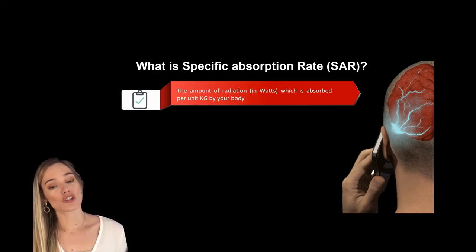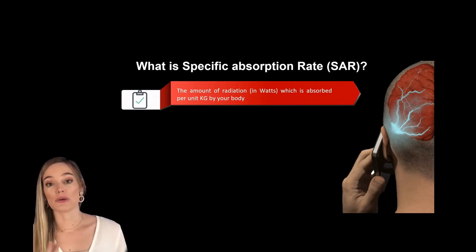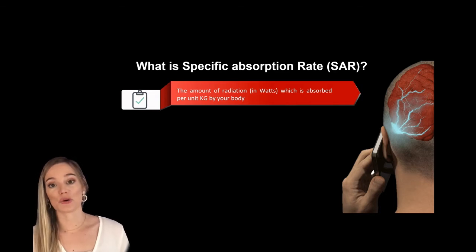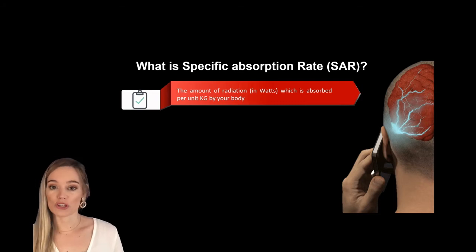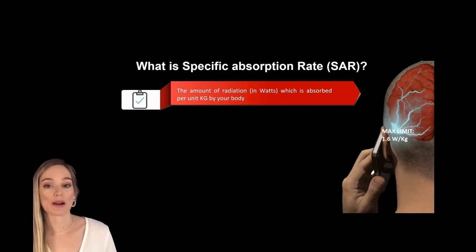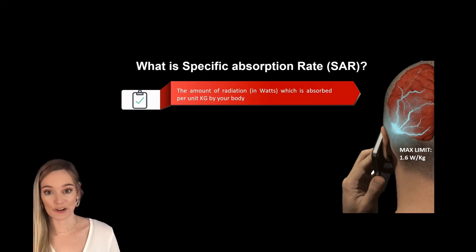Your hearing aids are class 2 medical devices, which means they have to comply to the FDA regulations, to the medical device directive regulations, and to your radio equipment directive regulations. All of which require the SAR rate to be below 1.6 watts per kilogram.